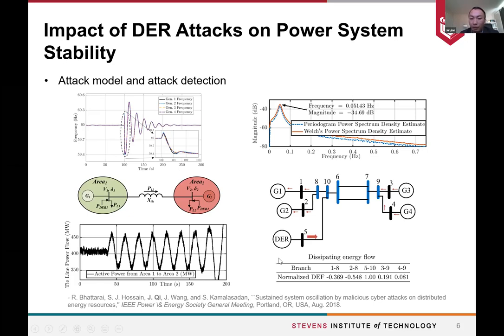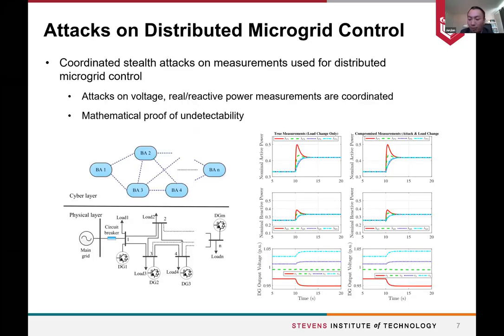If the magnitude is large enough, the protection system may operate and disconnect components. To address this problem, we have an attack detection approach based on domain knowledge. By implementing the dissipating energy flow approach, we can identify the source of this type of attack, and if we disconnect that source — such as the DER at bus 5 — we can reduce the oscillation and address the system stability issue.